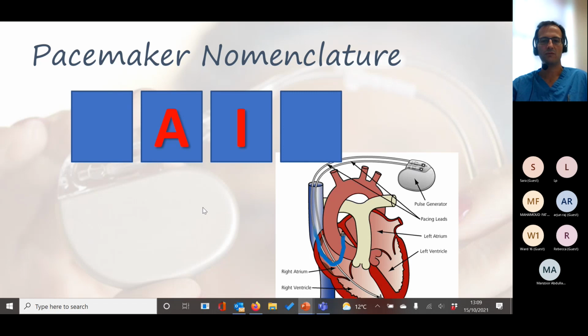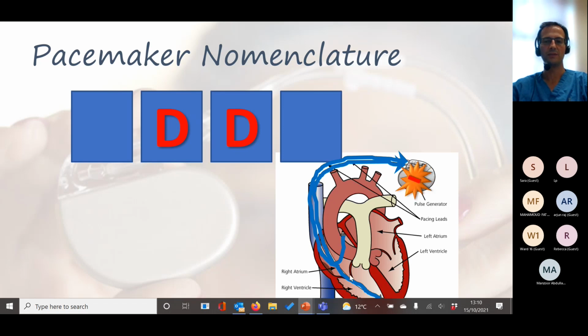The second letter along refers to what chamber it listens to, and the third letter refers to what it does in response to that. So A means it listens to the atrium, and if it sees a signal in the atrium, then it doesn't pace the atrium, which is generally what you want. A V and an I means that it listens to the ventricle, and if it sees a ventricular stimulus, it inhibits the pacemaker. More often, you get a D in there because you want it to stimulate the ventricle if it doesn't see anything and not stimulate the ventricle if it does see something. So you don't want it just to be inhibited.